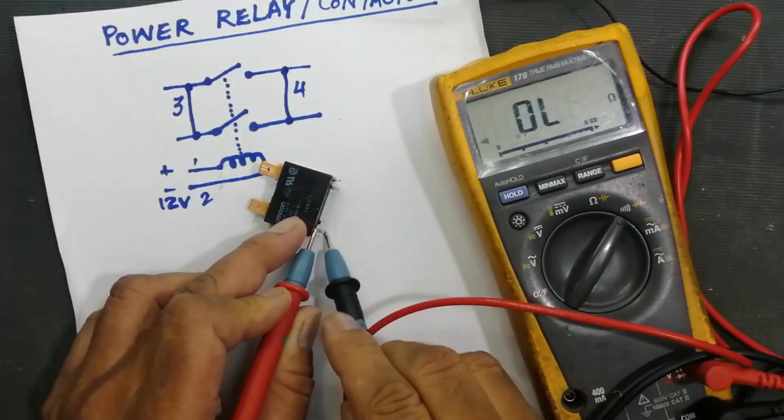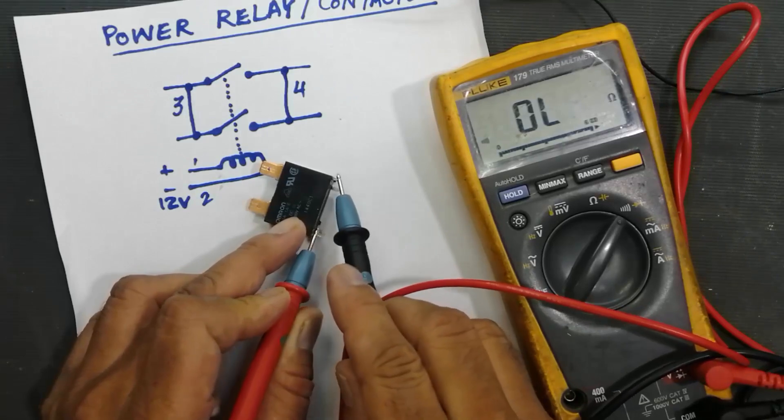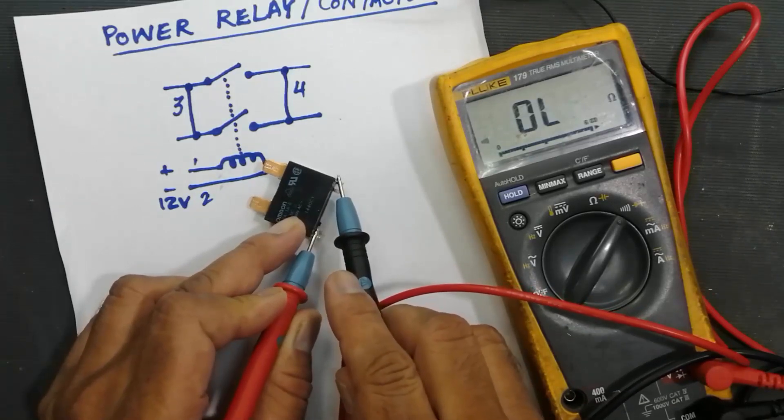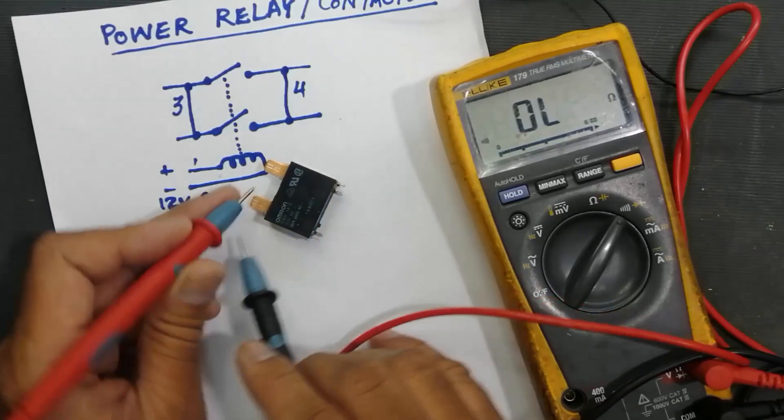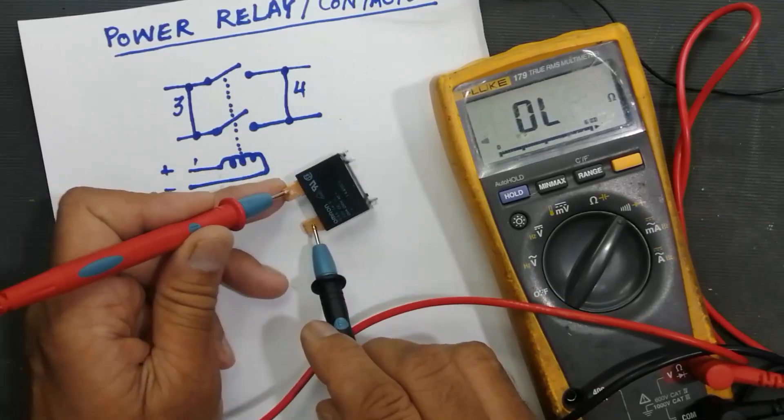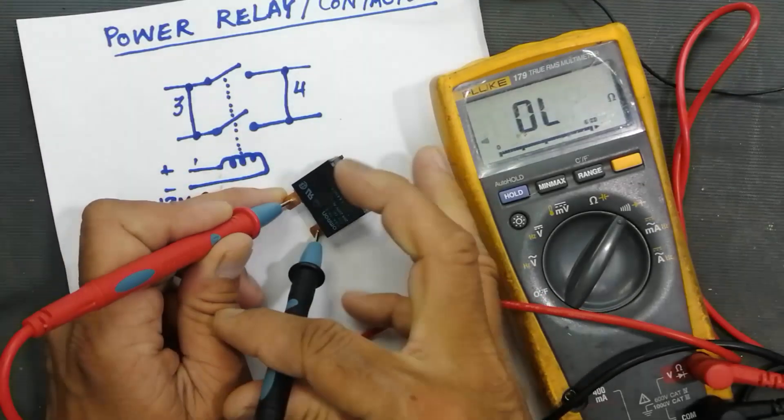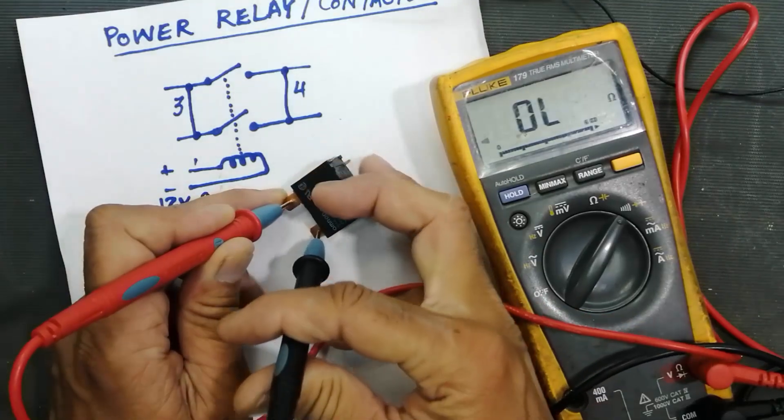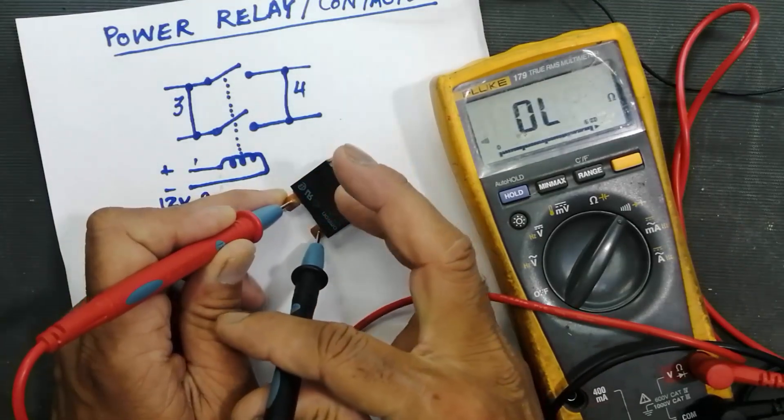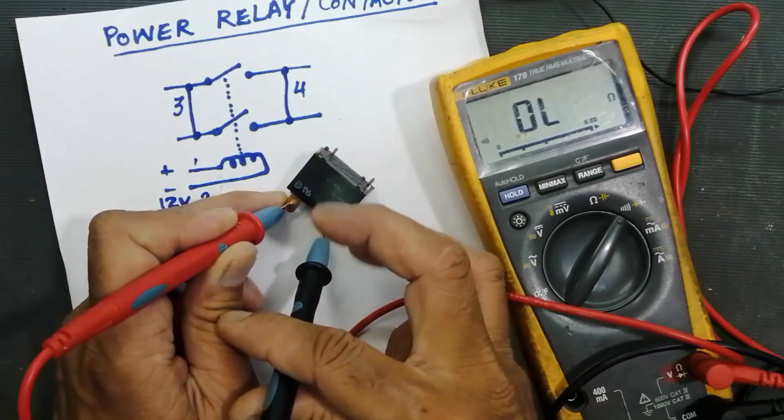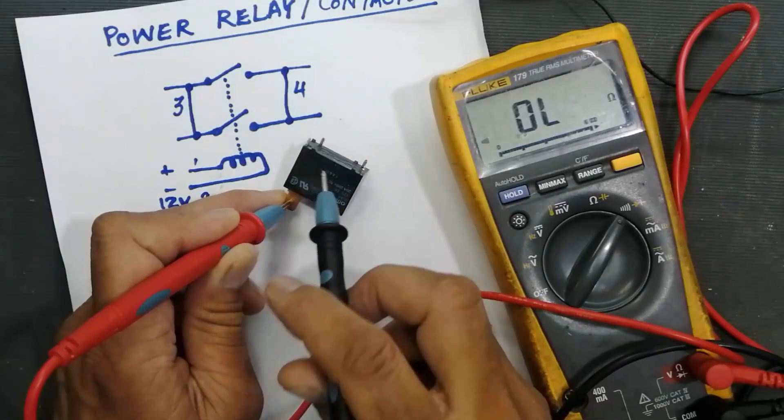And if we apply voltage at the coil point and it does not make the points, that means the relay is bad. And here, when you connected here and we applied coil voltage, control voltage, and the relay does not make connection, the relay is bad.